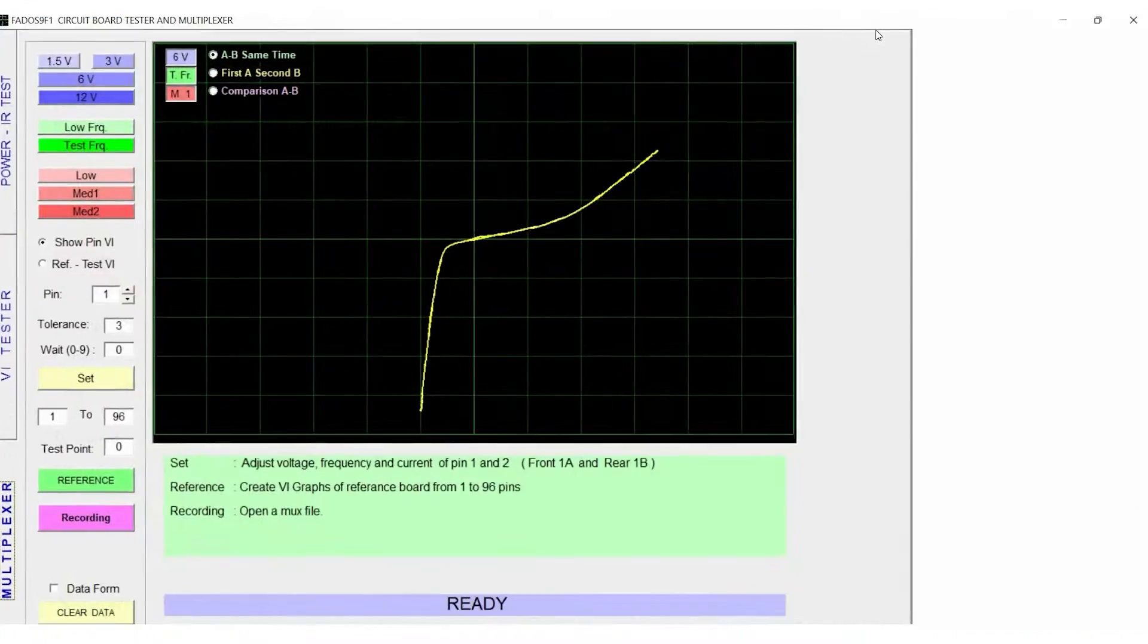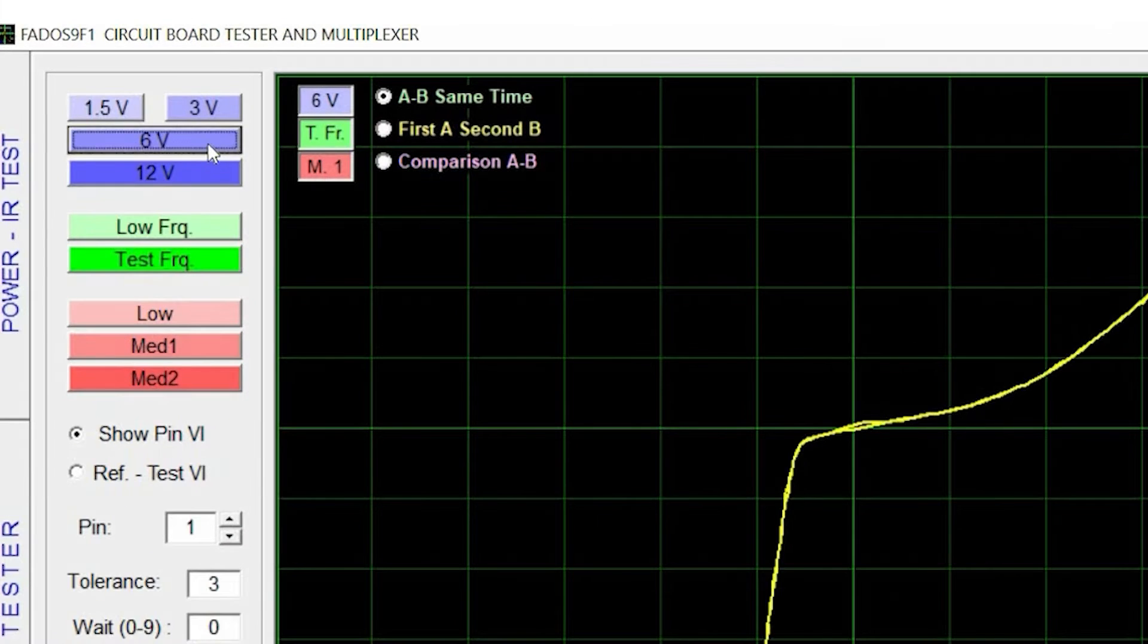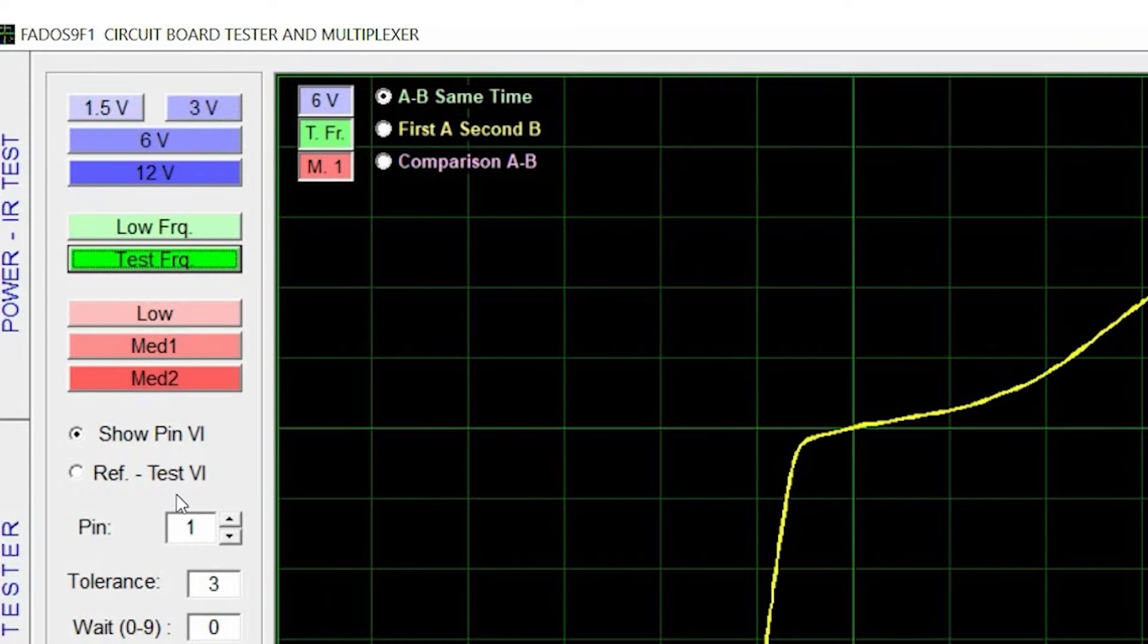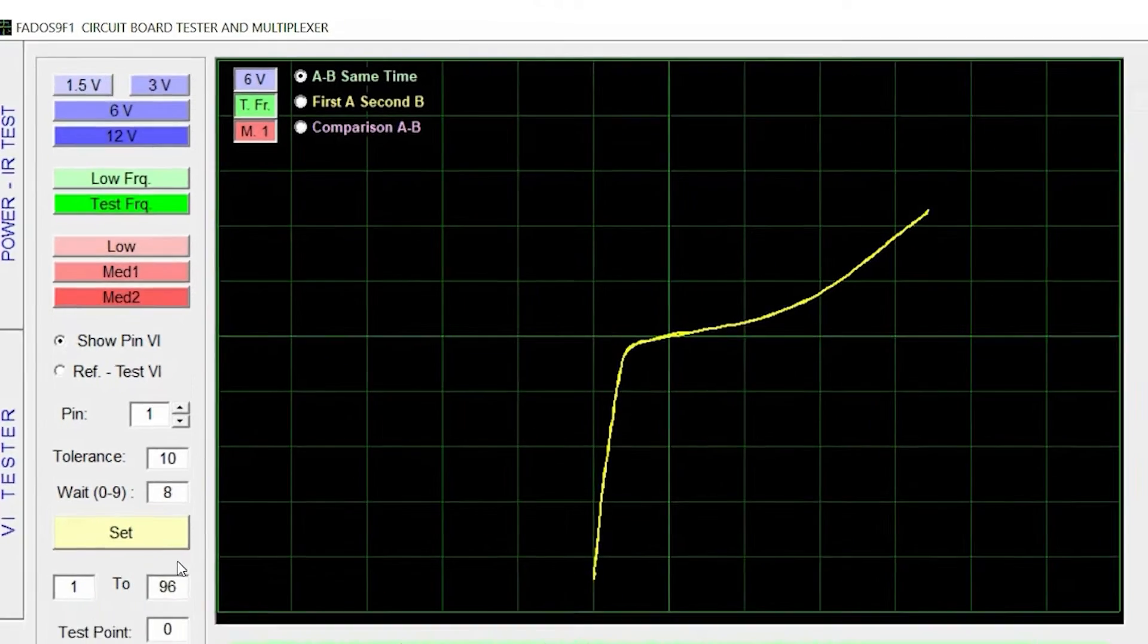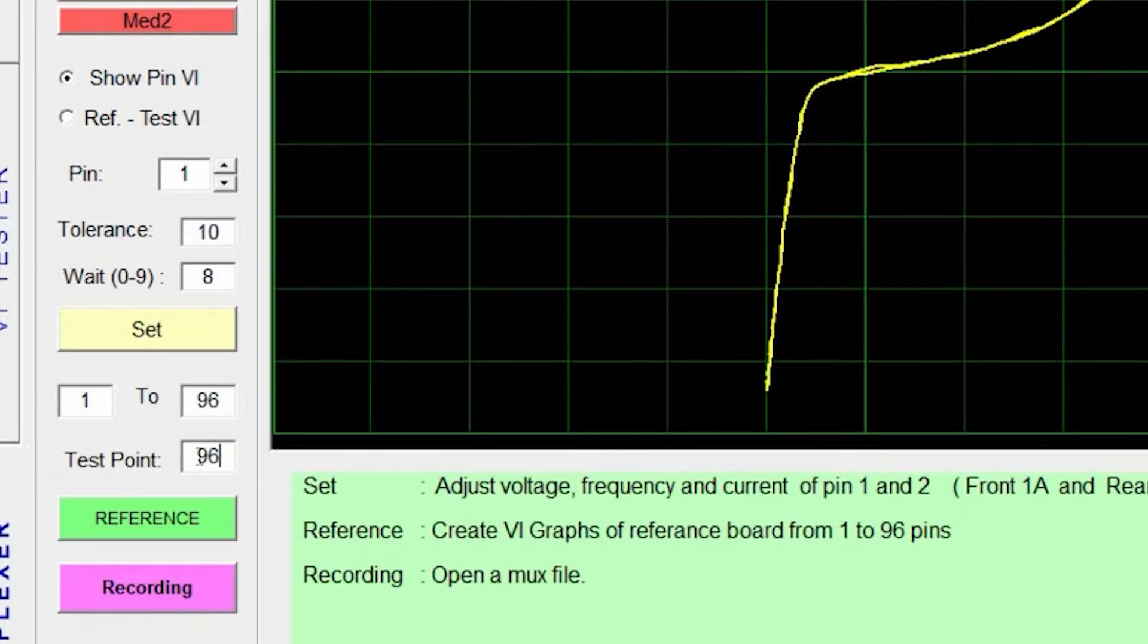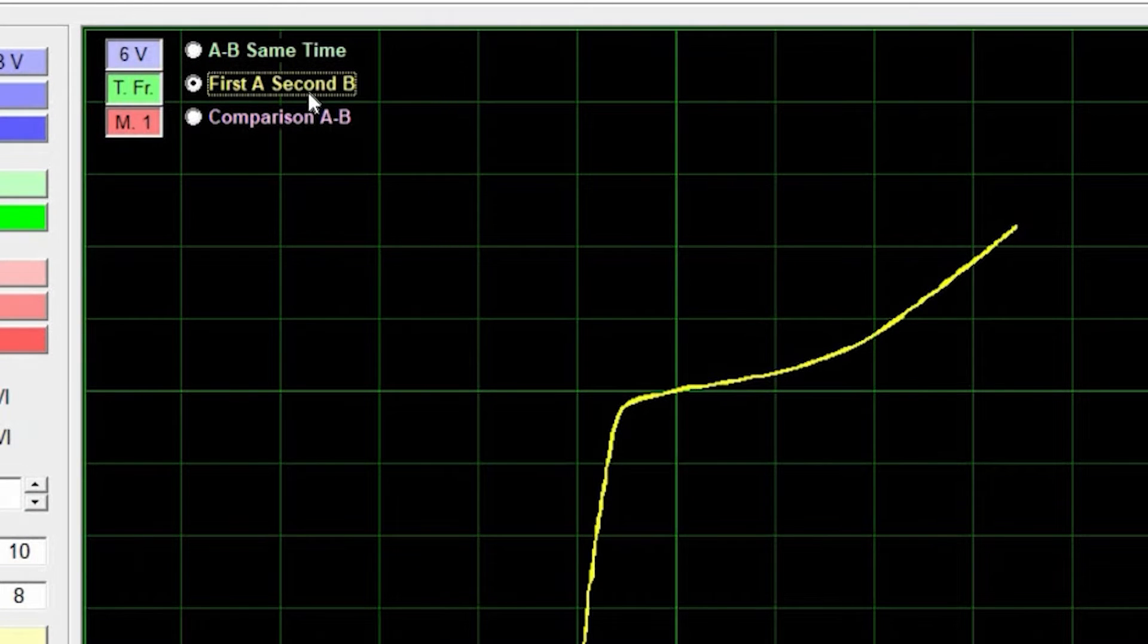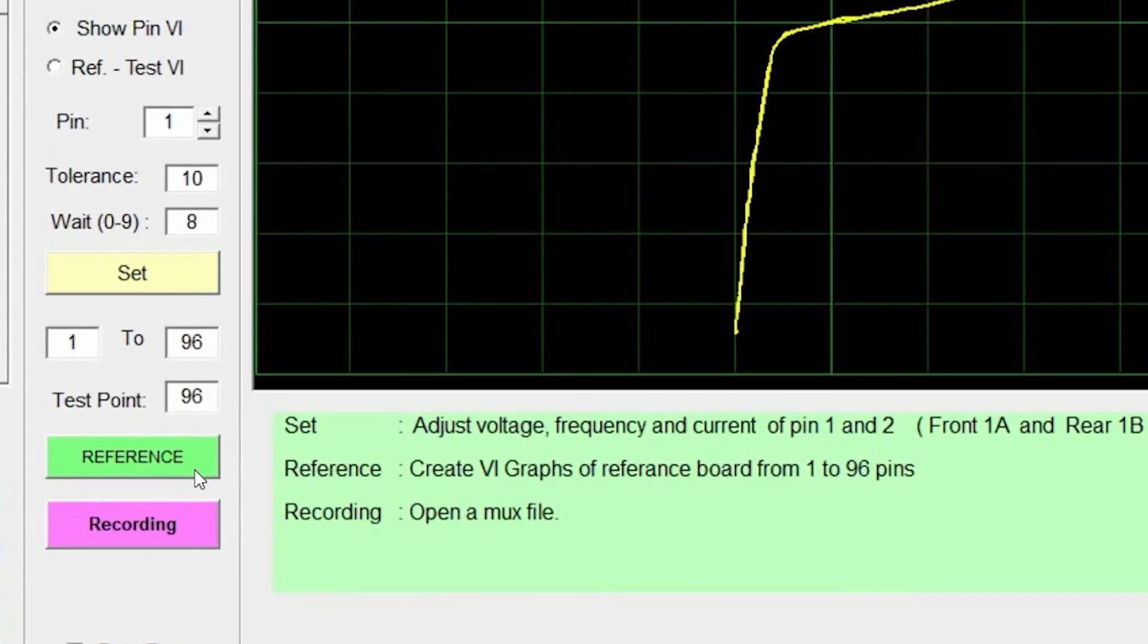Options used for troubleshooting are placed on the left-hand side of the software panel. Select the required test voltage, frequency, current, and tolerance. Select the wait time between 0 to 9. Enter a required number of test points from 1 to 96. And choose the manner in which you would like to save the data, click on Reference.